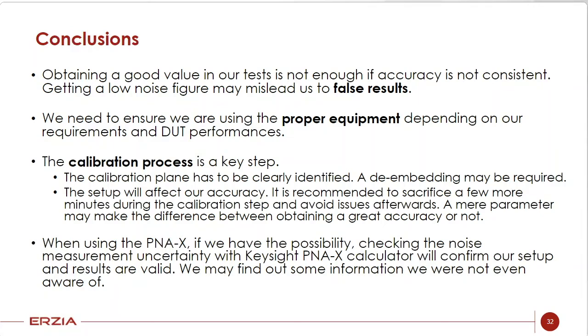a de-embedding may be required if you place additional adapters or other items between the calibration plane and the device under test. The setup will affect the accuracy, of course, so it's recommended to sacrifice a few more minutes, a little bit of effort during the calibration step in order to avoid issues afterwards. You can have a big difference at the end in the accuracy if you don't do that properly.